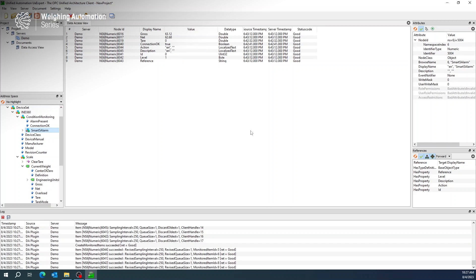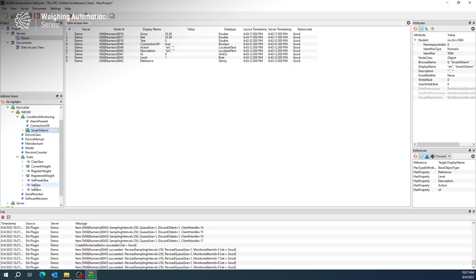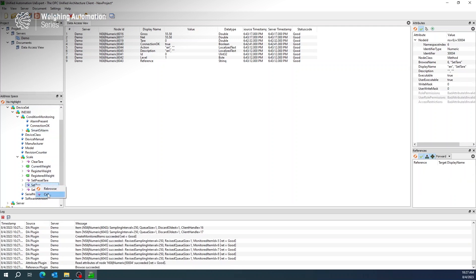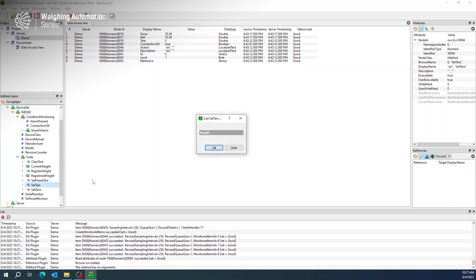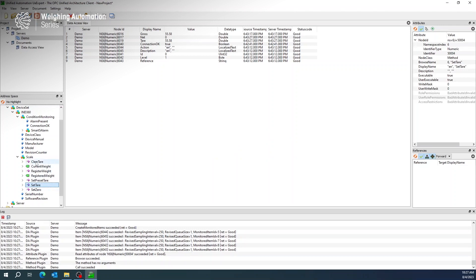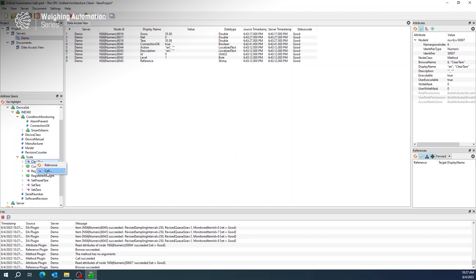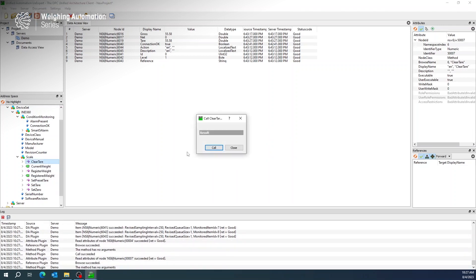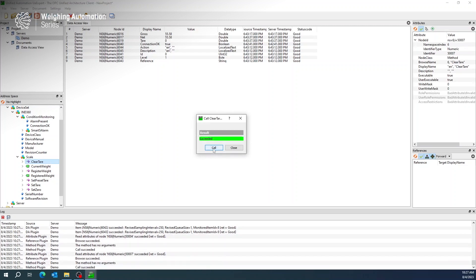Basic operations such as Zero, Tare, and Clear Tare are also possible using OPC UA. Let's call a tare function. For example, let's right-click on Set Tare and click the Call button. Immediately we can see that the tare is completed by looking at Gross and Net Weight. And now, as we clear the tare, we once again see Gross, Net, and Tare Weights change as we would expect.